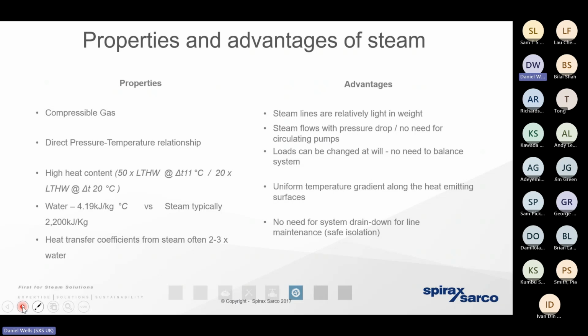Notably, it's a compressible gas, which means at a high pressure, we've compressed that volume, so we can now move it in a very, very small and cost-effective infrastructure without the need for those circulating pumps as we would do with a water-based system. We've got that pressure-temperature relationship. If we know the pressure of the steam, we know its temperature. That doesn't apply to a water-based system.